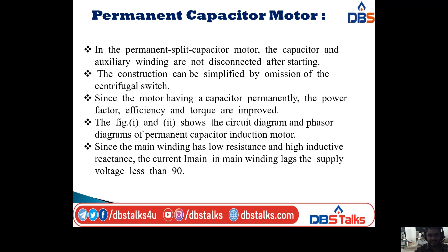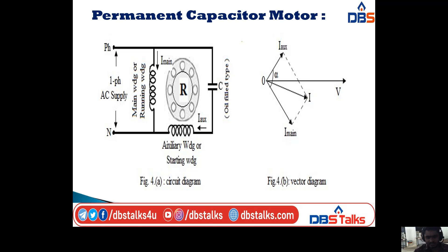The slide shows the circuit diagram and phasor diagram of the permanent capacitor induction motor. On the left side we have a circuit diagram, and on the right side we have the phasor diagram. In the circuit diagram, we are taking two windings: main winding (running winding) and auxiliary winding (starting winding). We are taking a capacitor in series with the auxiliary winding. In this method, we are not using any switch — there is no centrifugal switch, unlike the previous three methods.